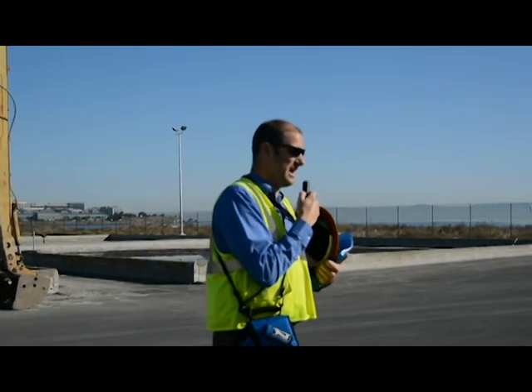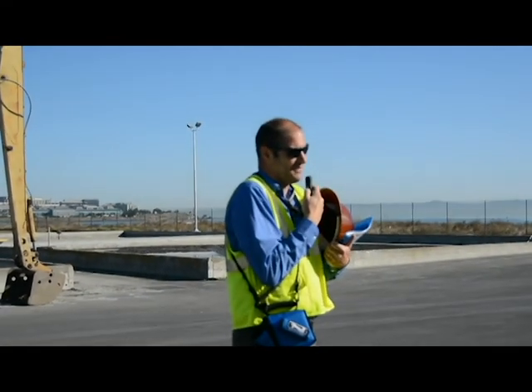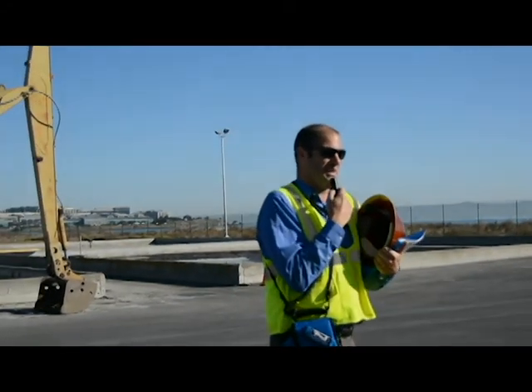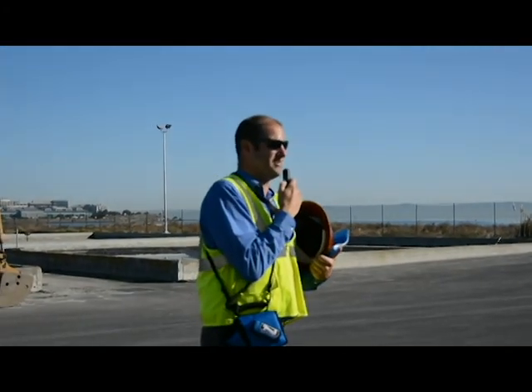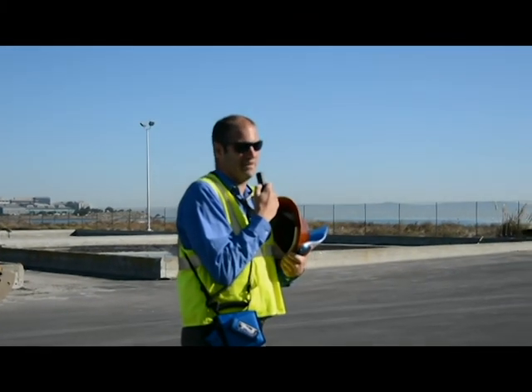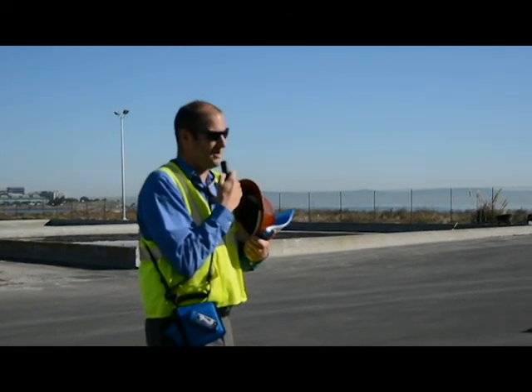Which that grinder actually leads to problems for us, because again, we get everything from ice cream scoops to metal pieces, whatever someone can flush down a toilet on a plane can come to us. As you grind up the disposable napkins and things like that, it gets fine parts that then get through. So we have major issues with our valving around here as they just get gummed up with fibrous material and rags. And so we're going through a whole replacement schedule on all of our internal valves as well. It's going to take a while.